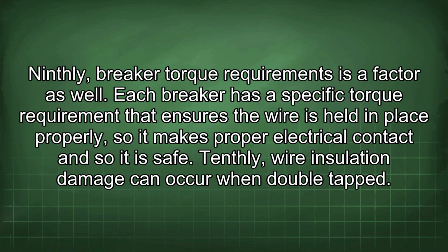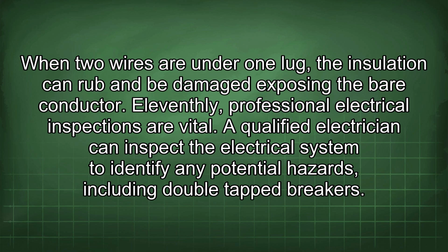Ninthly, breaker torque requirements are a factor as well. Each breaker has a specific torque requirement that ensures the wire is held in place properly, so it makes proper electrical contact and so it is safe. Tenthly, wire insulation damage can occur when double tapped. When two wires are under one lug, the insulation can rub and be damaged, exposing the bare conductor.